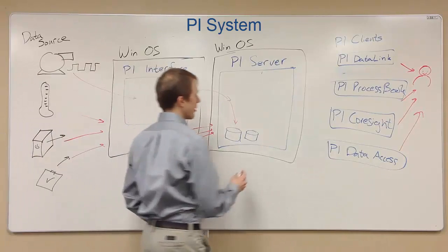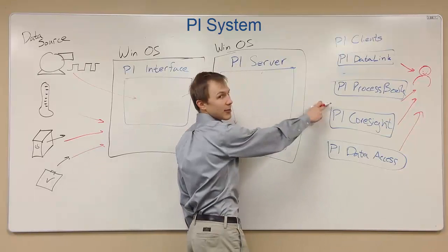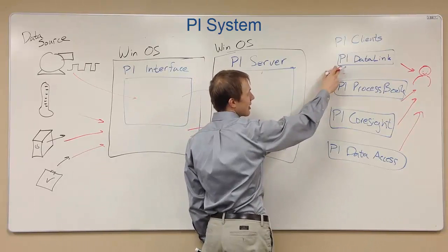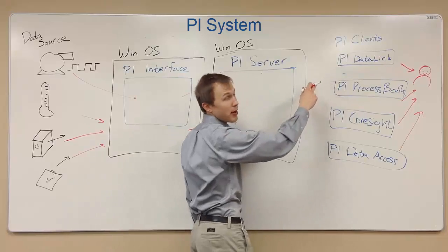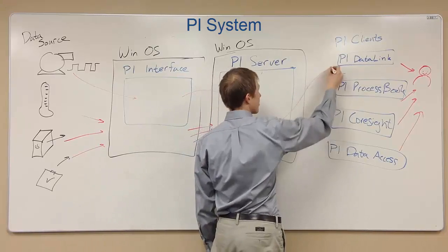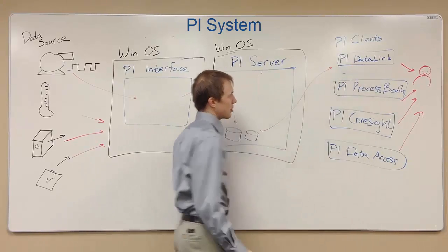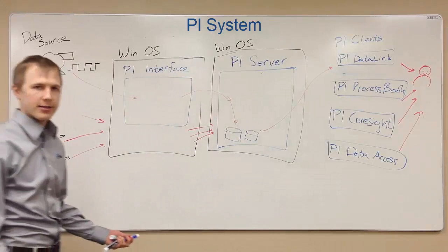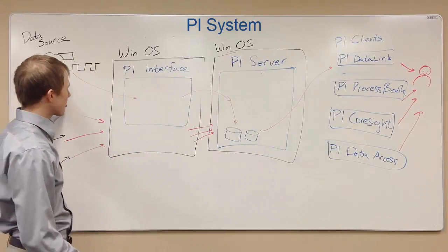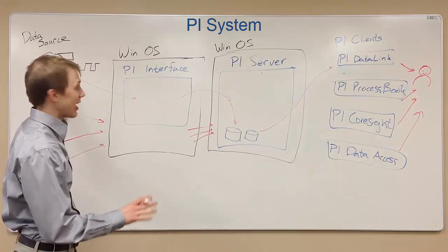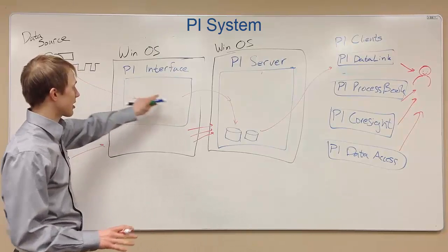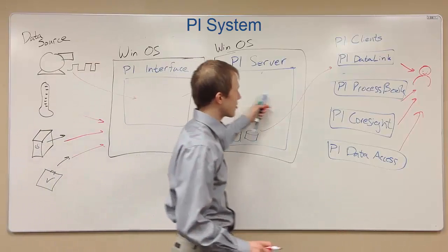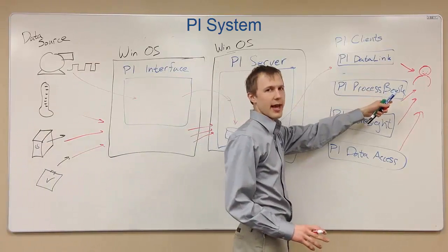From there, the PI Server responds to queries from clients. For example, DataLink will say, 'PI Server, I want to see the last seven days of data for that pump,' and the PI Server will serve out the data and show it to the user. That is a basic PI System: a data source, which is not made by OSI Soft, contacted by an interface, which sends the data to a PI Server, and then some way for users to see the data.